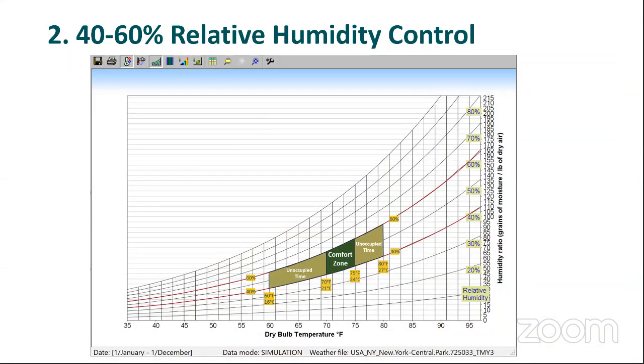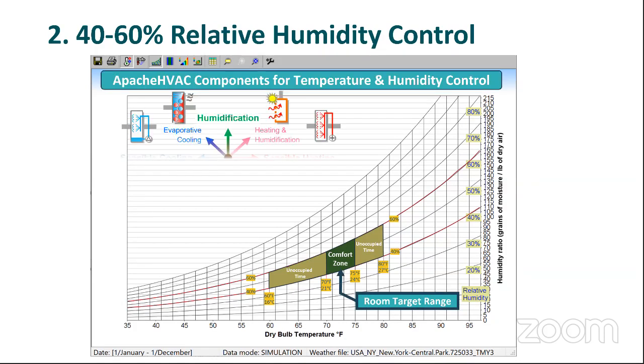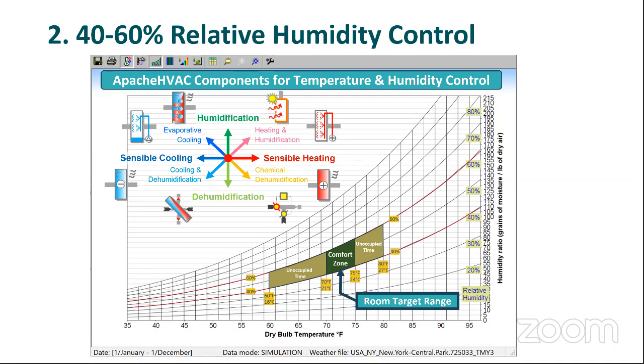Number two is relative humidity. ASHRAE has published documentation stating the most unfavorable survival for microorganisms is when relative humidity is between 40 and 60%. Here I'm showing the room target range. The IES Apache HVAC application has a range of components to control both temperature and humidity for any given space.